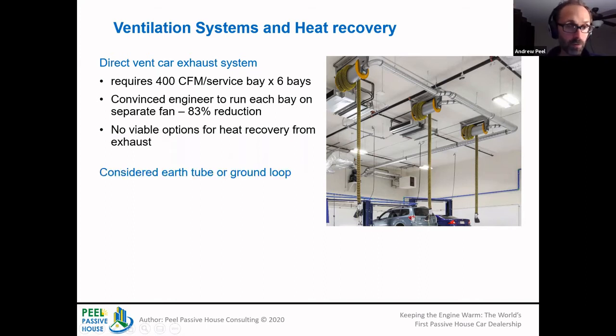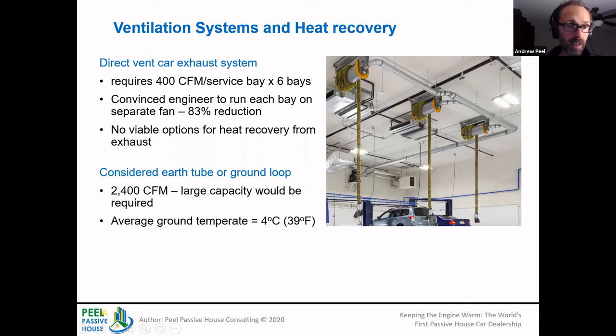We also considered an earth tube or ground loop, like a glycol loop outside. However, the 2,400 CFM is a huge capacity. It's running intermittently, but it turns on at potentially a high capacity, and we need to size the system to deal with the max load, even if most of the time that's not going to be happening. And the average ground temperature in the area is only 39 Fahrenheit, so there's not as much of a temperature uplift that we can get. There's also the danger of frost heave with the system. So that proved not viable as well. So we basically had to suck it up and deal with the extra heat loss.